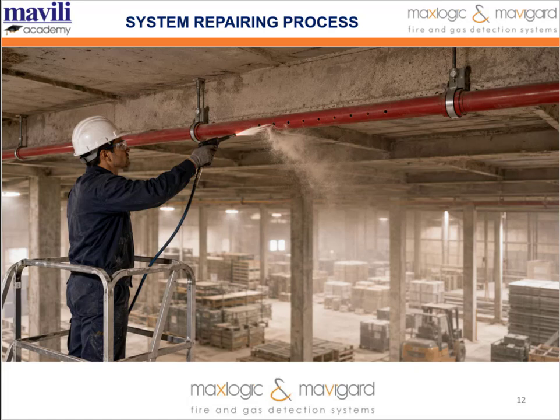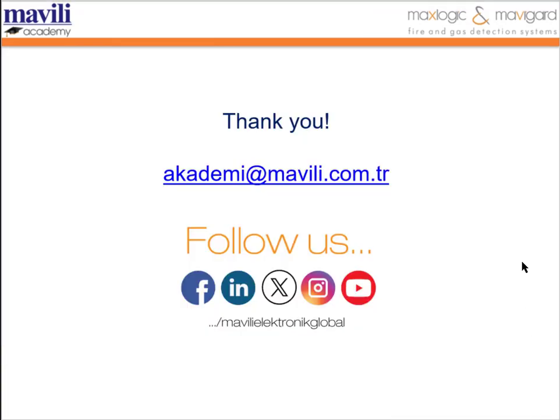The other point is maintenance and periodic checks. So in critical areas, simply installing the system is not enough. Its performance must be maintained through regular maintenance and testing, especially for aspirating smoke detectors. So filter check, airflow check, pipeline and sampling hole check. Also we should test the alarm levels, and device and control panel communication check should be performed.